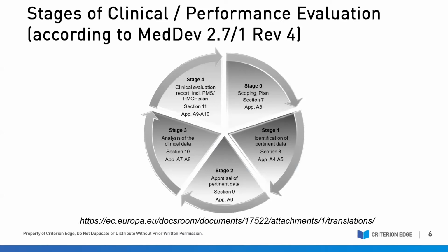Now in stage 3, this is where you will be analyzing the data and making conclusions regarding compliance with essential requirements, the contents of the informational materials, such as the label and the IFU, and a discussion of residual risk and uncertainties or unanswered questions. This is where you will have an assessment of whether these are acceptable risks for CE marking, and you may also describe how this risk will be addressed during post-market surveillance activities. Only after all of these stages can the report be finalized.